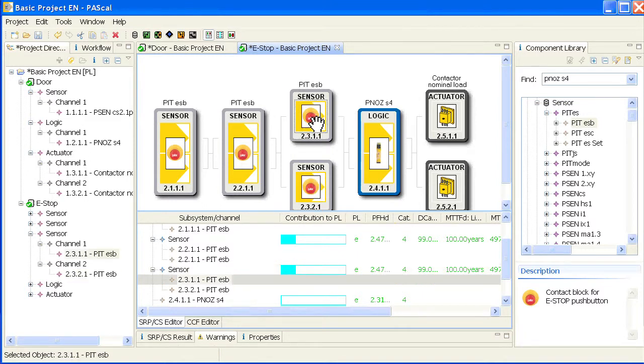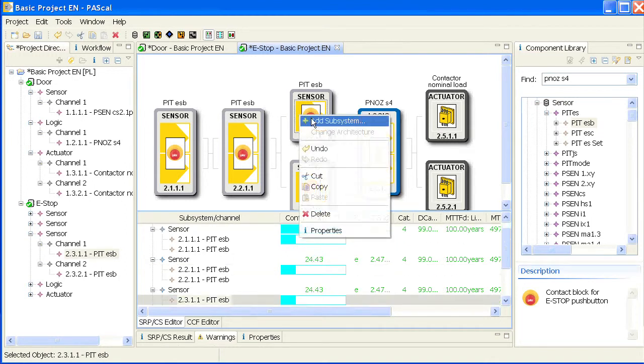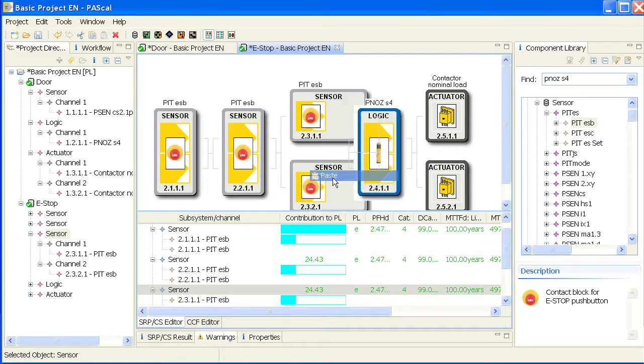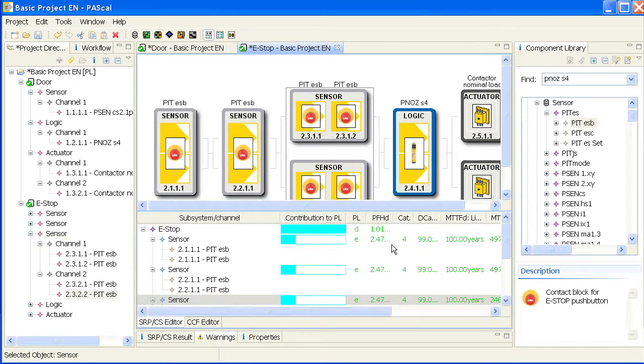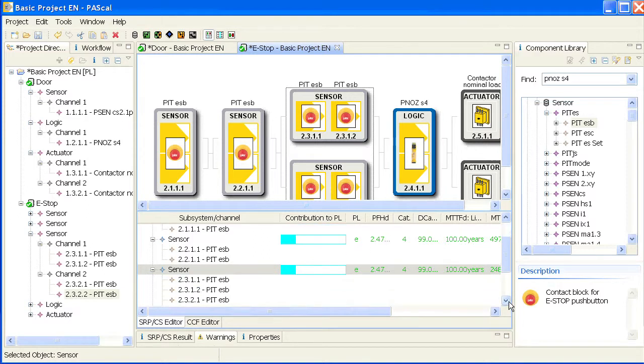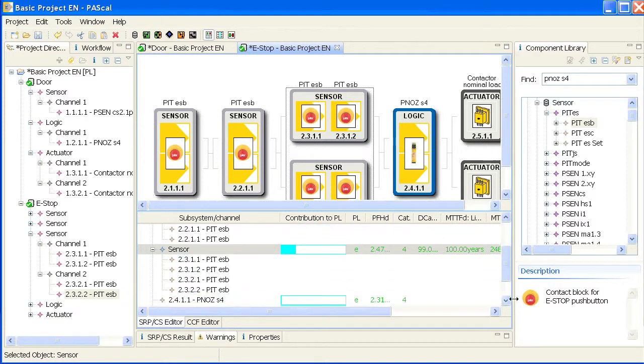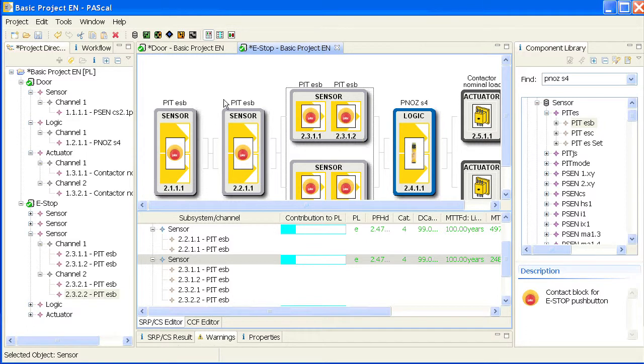But if I right now copy and insert and paste another one right here and another one right here, I've got two sensors in one subsystem. And the tricky thing that has something to do how the 13849 calculates it, the two together have the same safety result as the single sensor right here. And you will find that this is true in many cases even if you add 5, 6, 7, 10 sensors in one queue. So if you have to add more, this might be the more appropriate way to show it.